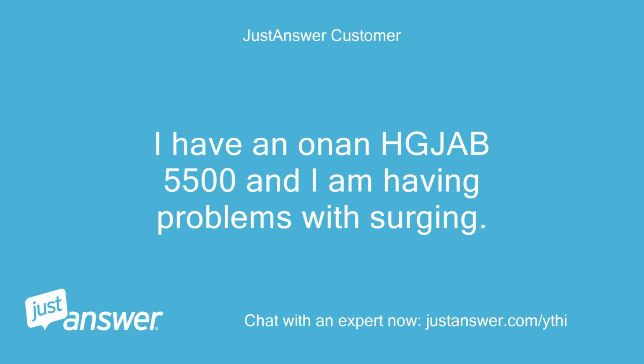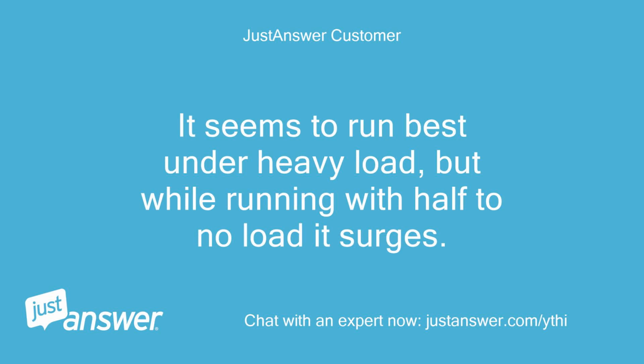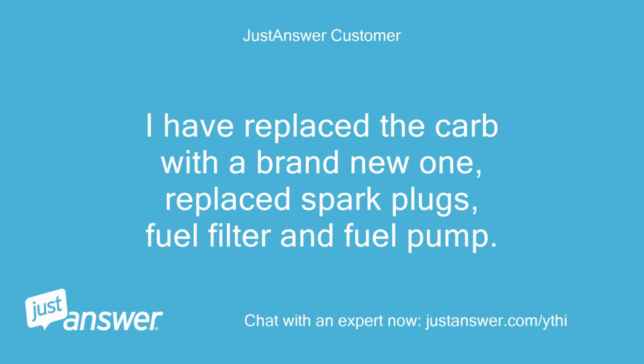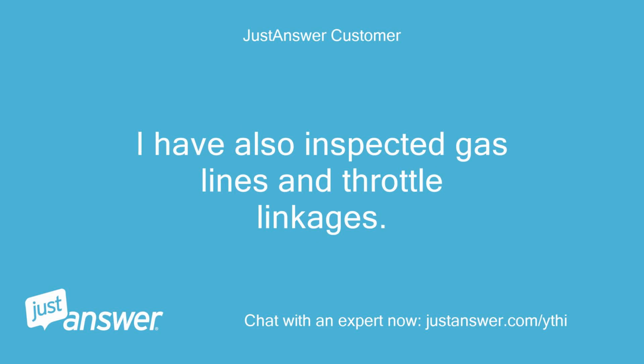I have an Onan HGJAB 5500 and I am having problems with surging. It seems to run best under heavy load, but while running with half to no load it surges. I have replaced the carb with a brand new one, replaced spark plugs, fuel filter and fuel pump. I have also inspected gas lines and throttle linkages.